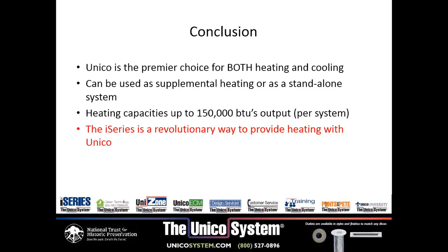So what a lot of people do with radiant floor is they have a boiler anyway. They'll put in a slide-in hot water coil, and then for the shoulder season, the in-between season, they'll have the boiler run sending hot water to our coil. So they get the heat immediately. The other way is we can use it, again, up to 150,000 BTUs of heating with the hot water coil.